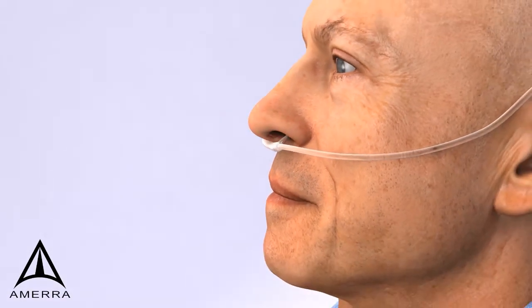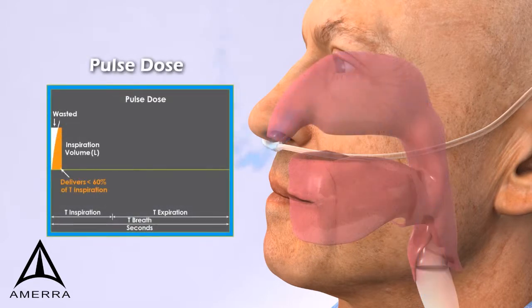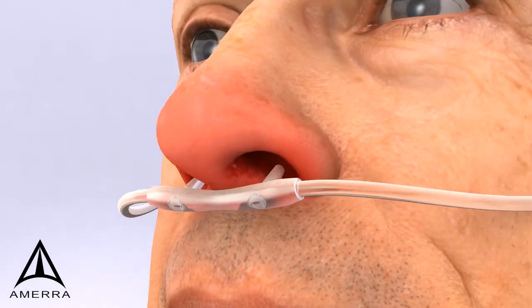The majority of portable concentrator systems utilize a pulse dose delivery. The patient triggers the pulse during inhalation. Similar to continuous flow, the bolus delivered by pulse dose systems exceeds the inhalation rate of most patients. As a result, the patient only receives a portion of the prescribed dose while the remainder is lost to retrograde flow. Similar to patients receiving continuous flow therapy, the effect of retrograde flow often causes nasal irritation and nose bleeding.